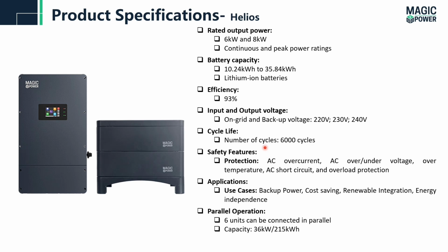The life cycle of the battery is 6000. Safety features: over current, over and under voltages, over temperature, and short circuit and overload protection. These are the integrated protection features of this system. Application scenarios for these systems are backup power, energy independence, and cost saving. Parallel operation, as I mentioned earlier, 6 units can be connected in parallel maximum. The capacity for the system will be a rated output power of 36 kilowatt, while the storage capacity will be 215 kilowatt hour.